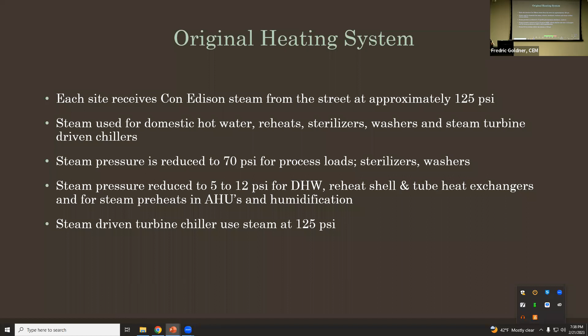So in about 2016, we said, what can we do? And we went into design of replacing the steam system with a hot water system. Overall, the project was 6 years in the making, 3 years worth of designs and permits, and 3 years of construction. We ended up buying prefab houses that we lifted up to our roofs, and we had 2 boiler plants. One of the boiler plants from Memorial Hospital had 12 boilers. 4 of them were dual fired because we needed a secondary fuel source to provide heating for the hospital in case we lost natural gas.